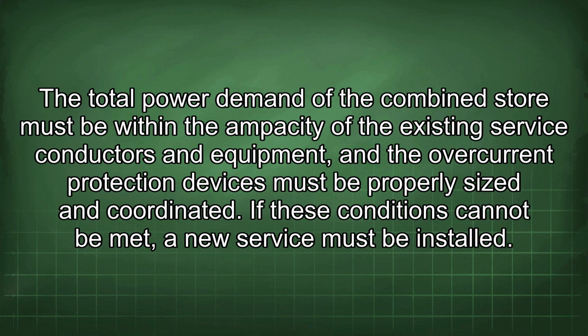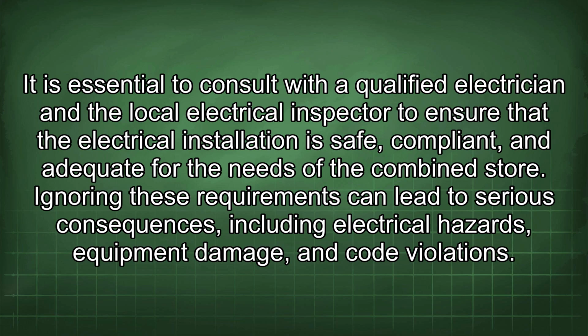The total power demand of the combined store must be within the ampacity of the existing service conductors and equipment, and the overcurrent protection devices must be properly sized and coordinated. If these conditions cannot be met, a new service must be installed. It is essential to consult with a qualified electrician and the local electrical inspector to ensure that the electrical installation is safe, compliant, and adequate for the needs of the combined store. Ignoring these requirements can lead to serious consequences, including electrical hazards, equipment damage, and code violations.